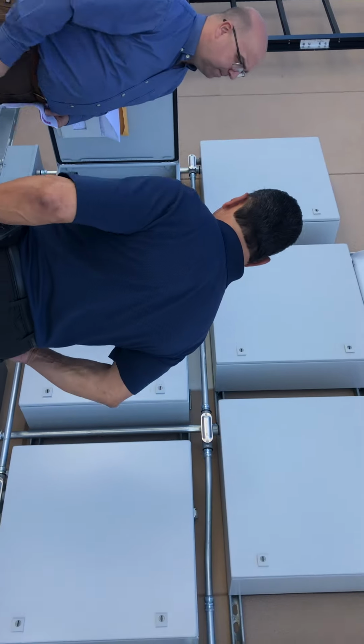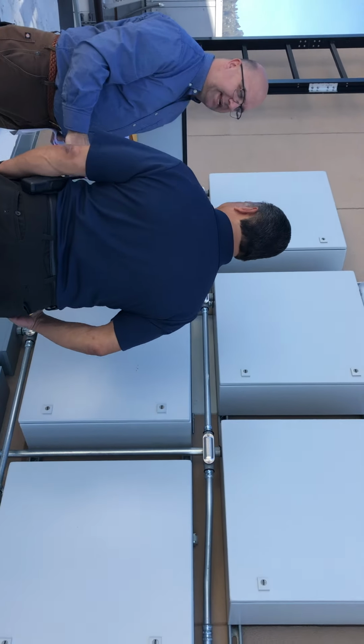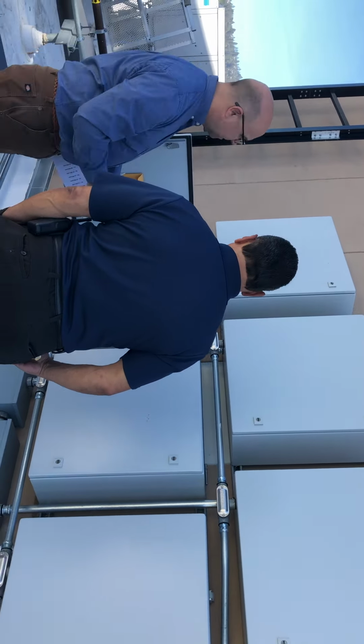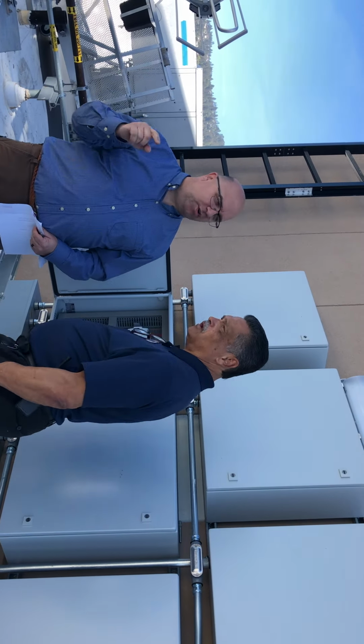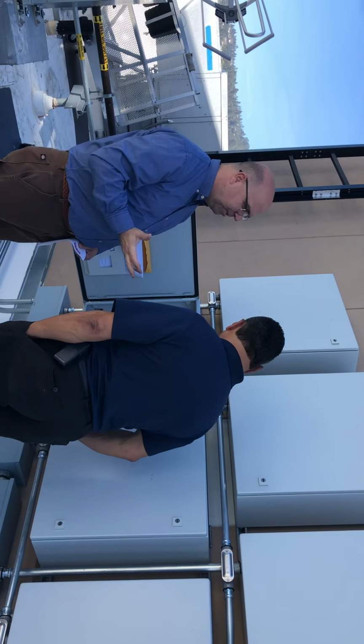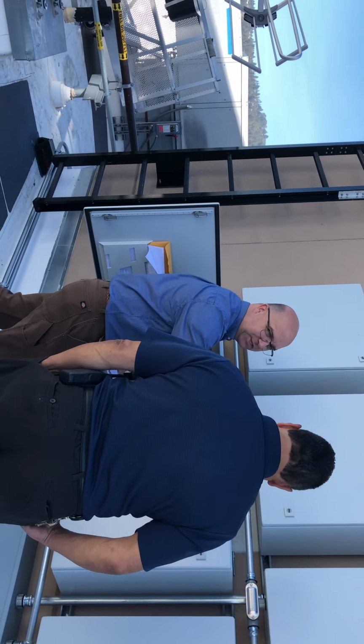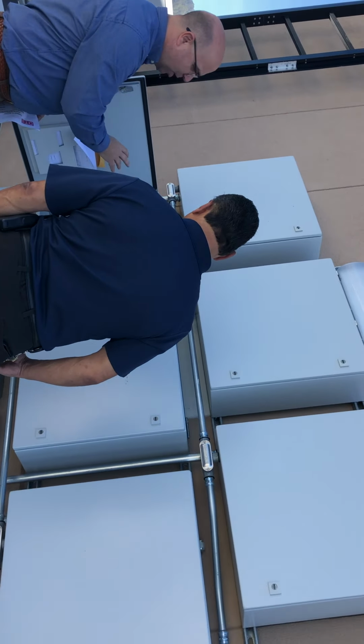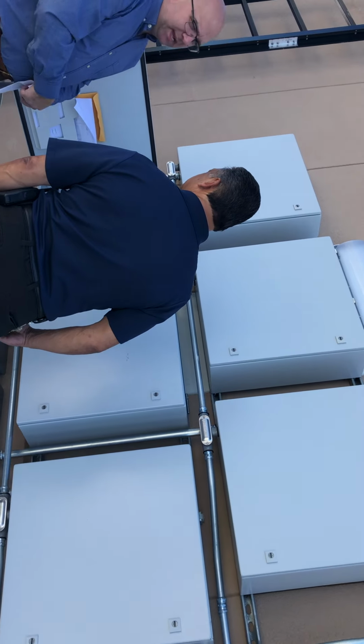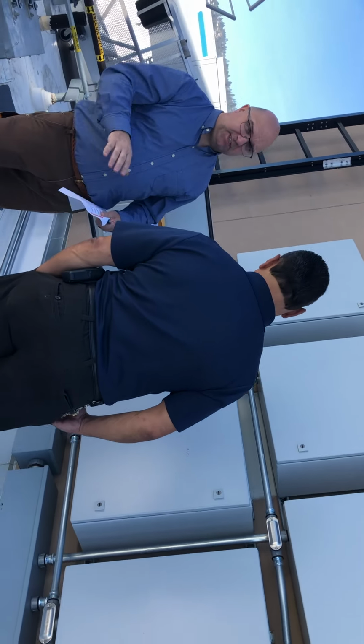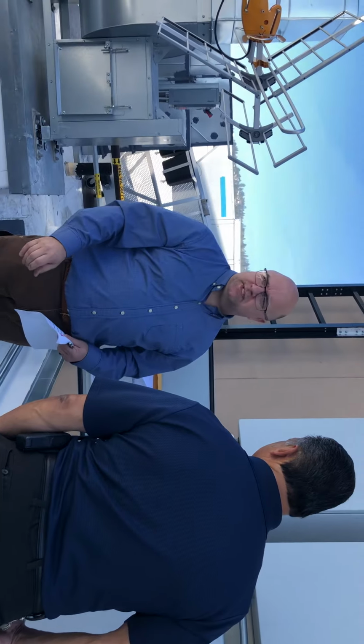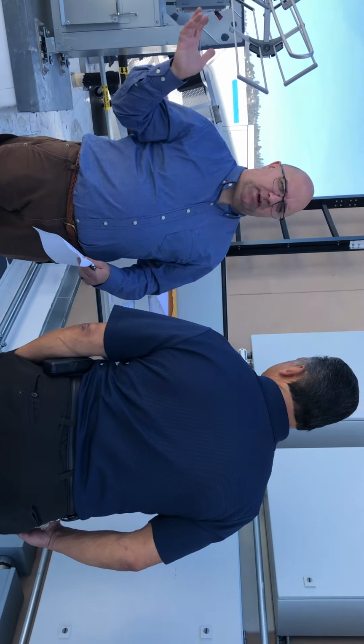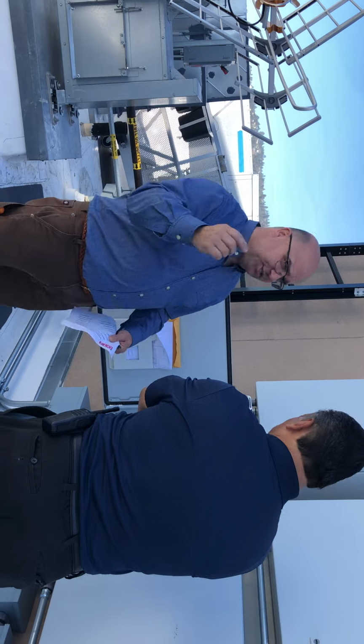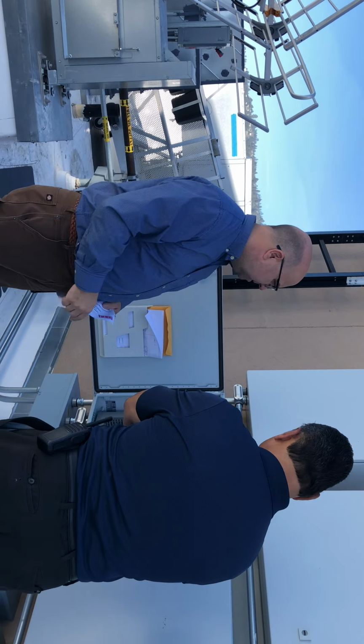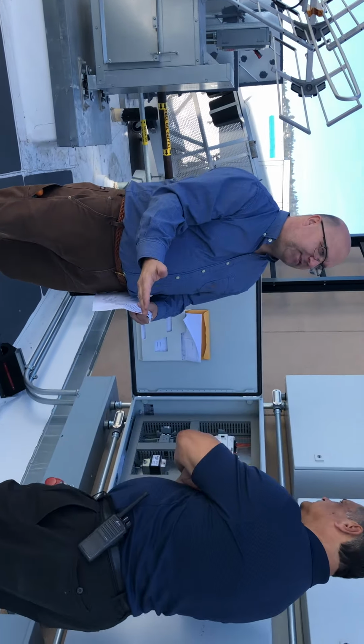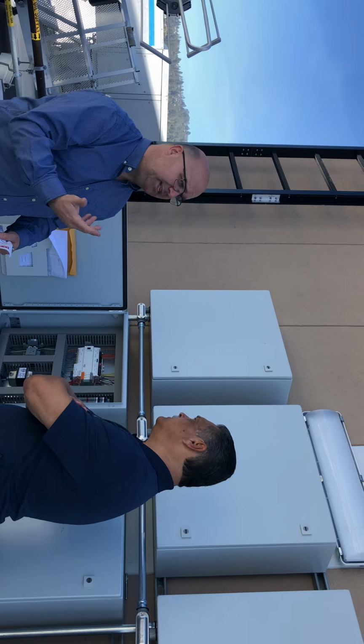Okay, so six panels, all identical. They run the makeup air units RD1 through 6. Before we're out of here, we'll have an engraved label showing which one is which. These not only run the makeup air units that serve the various floors and side portions of the floors, but many of the miscellaneous exhaust fan statuses are also run into here as well, so they serve a dual purpose of controlling equipment and reading miscellaneous statuses.